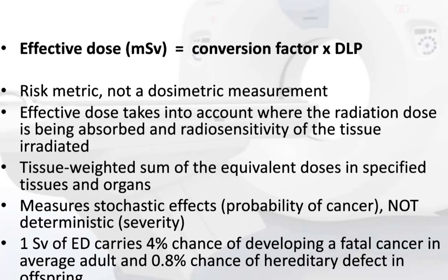Effective dose is a coefficient K times DLP, so effective dose is proportional to DLP. It is a risk metric, not a dosimetric measurement. Effective dose takes into account where radiation dose is absorbed and the radiosensitivity of the tissue irradiated. One Sievert of effective dose carries a 4% chance of developing a fatal cancer in an average adult and a 0.8% chance of hereditary defect in offspring.